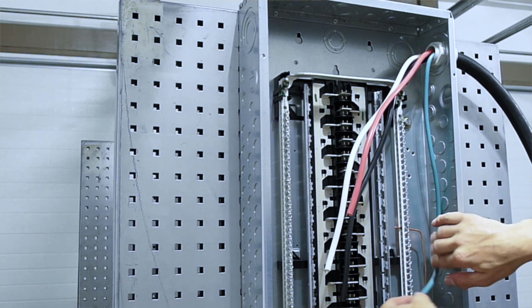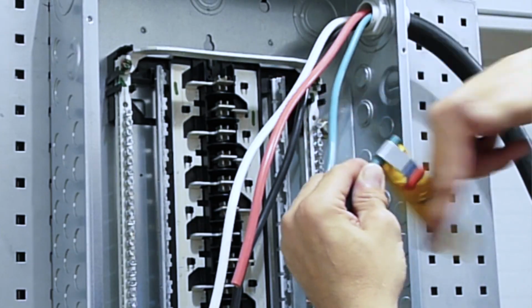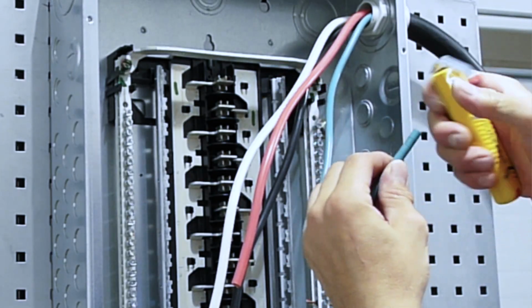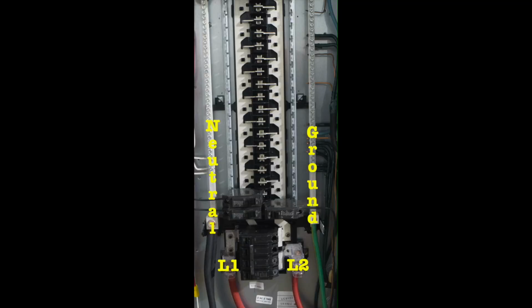Now let's connect the other end of the cable to the circuit breaker panel. Every main panel comes with 4 bus bars. On the right we have our ground, on the left we have our neutral, and the 2 middle ones, where we attach the circuit breakers, are L1, L2, the phase bus bars. If you are not sure where to connect these wires, please ask an electrician.